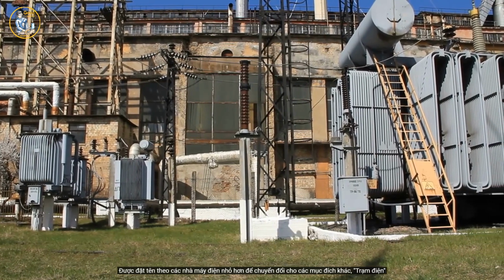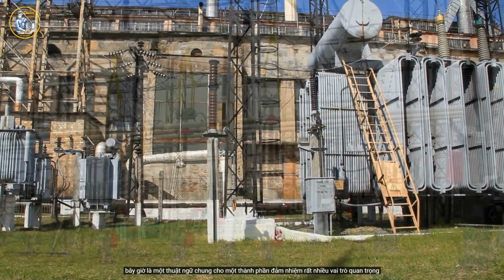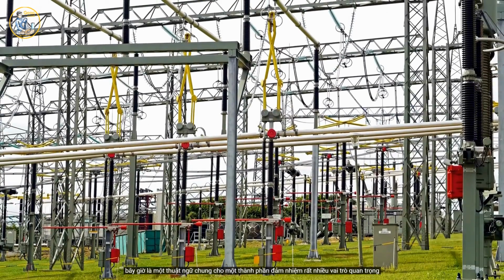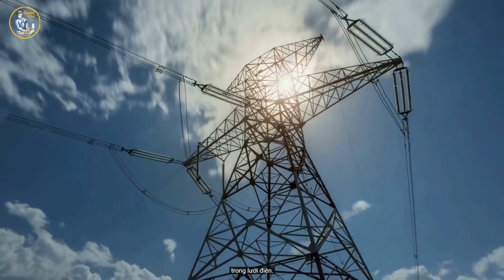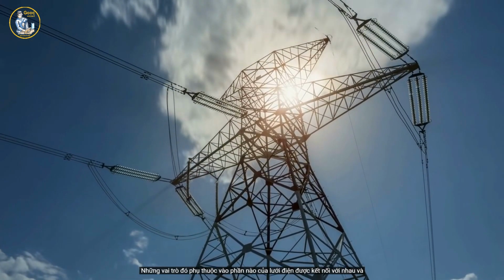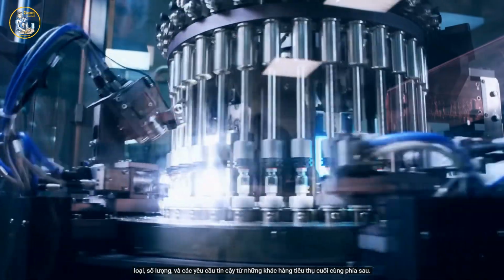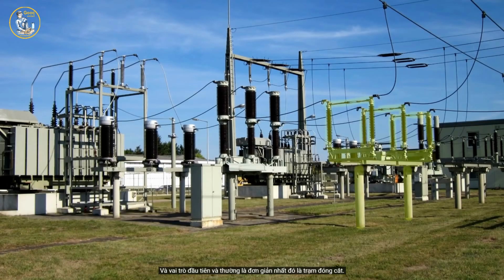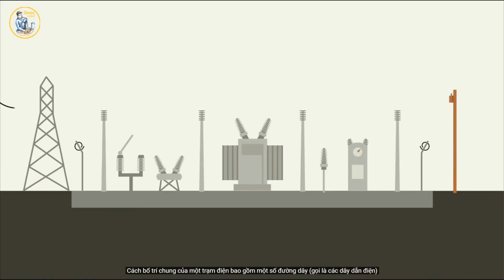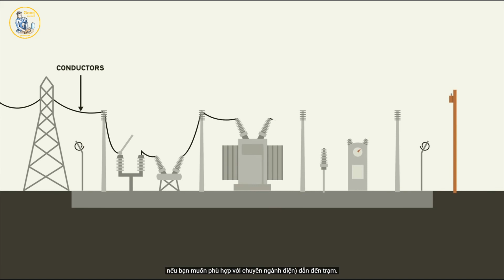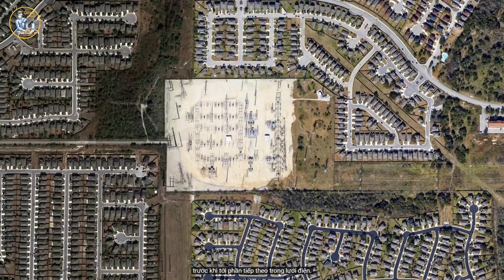Originally named for smaller power plants that were converted for other purposes, substation is now a general term for a facility that can serve a wide variety of critical roles on the power grid. Those roles depend on which parts of the electrical grid are being connected together, and the types, number, and reliability requirements of the eventual customers downstream. And the first and often simplest of these roles is switching. The general layout of a substation consists of some number of electric lines, called conductors if you want to fit in with the electrical engineers, coming into the facility. These high-voltage conductors connect to a series of some or many pieces of equipment before heading out to their next step in the power grid.